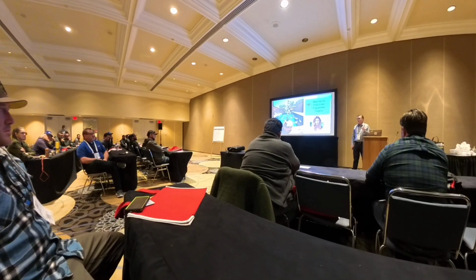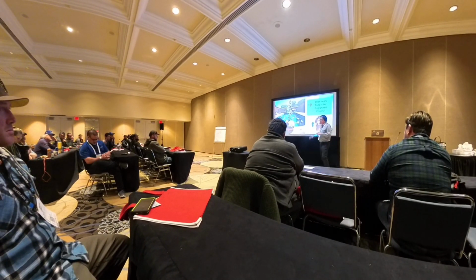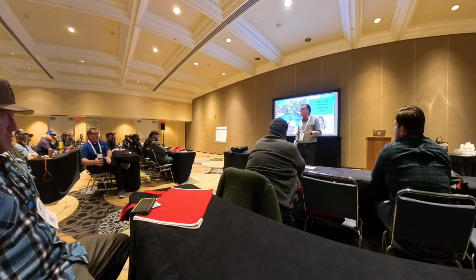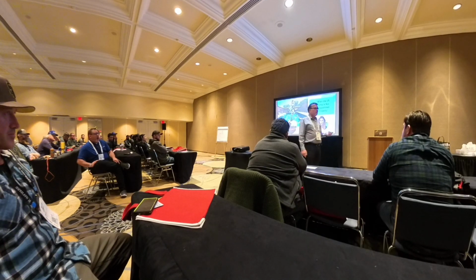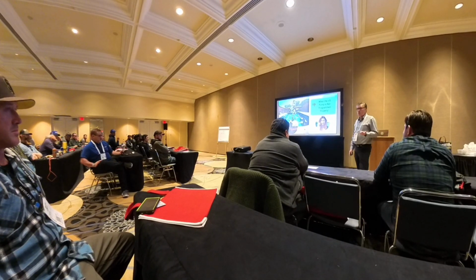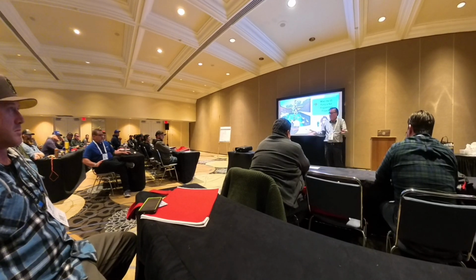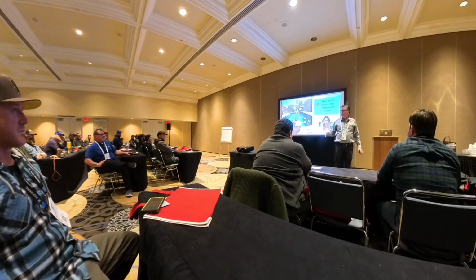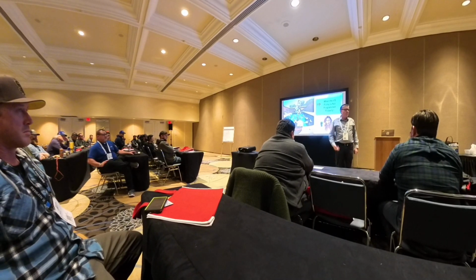So going into this, the hypothetical here is we did a like-for-like replacement, but you can't because it was a 1 horsepower single speed and now they're illegal. So they do the equivalent variable speed pump. Equivalent. Yeah, okay. So it's a like-for-like because you don't have to adjust the piping. You undo the unions and it fits perfect. And you turn it on and it's a lot louder because it's a more powerful pump. But that's not my problem. I'm the swap-and-run guy.